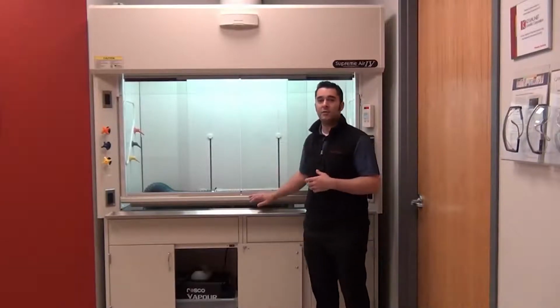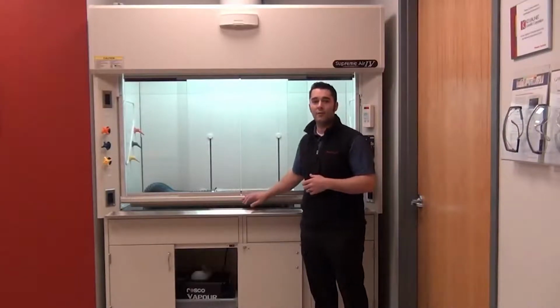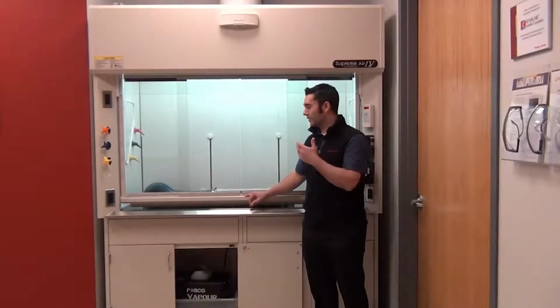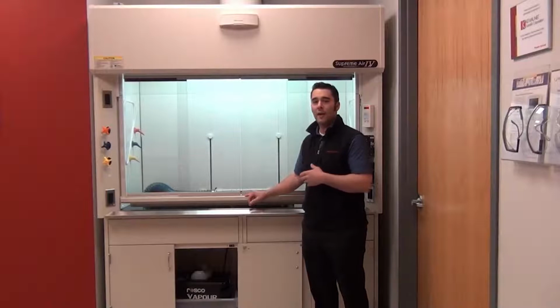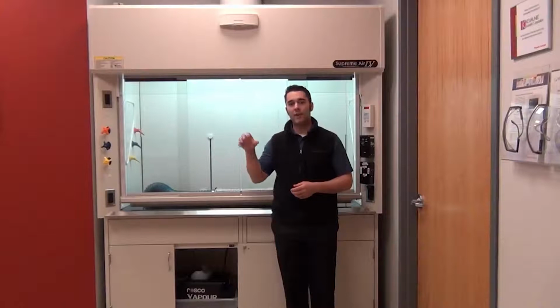Now we still tell people that it's a good idea to make sure, especially in fume hoods, that you have them recertified every year. Most facilities have a health and safety initiative that makes them recertify their fume hoods every year. And if you want a double check to guarantee that the Phoenix valves are still working properly, that's a good way to do it. So you can take a Phoenix Controls run fume hood that has a Phoenix Controls valve on it. You can actually shoot the face velocity on that fume hood on an annual or a semi-annual basis to verify that that Phoenix Controls valve is still working properly.